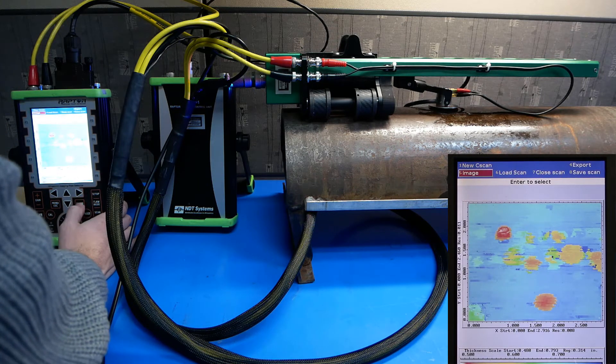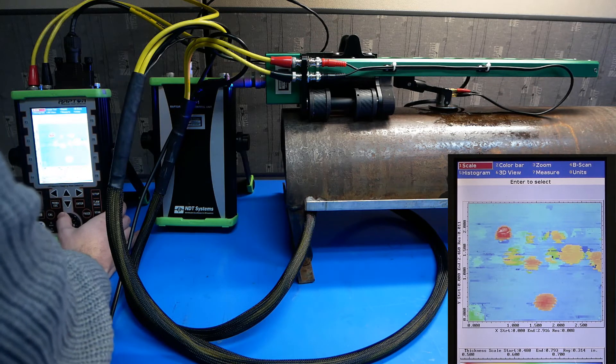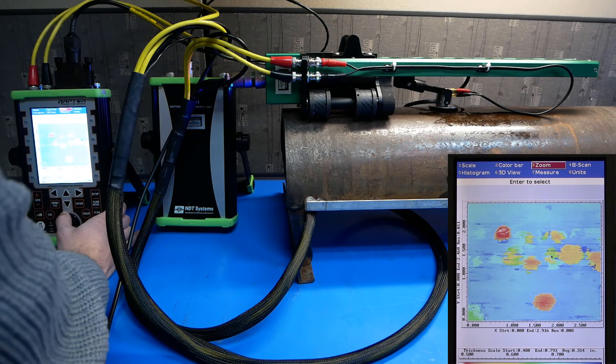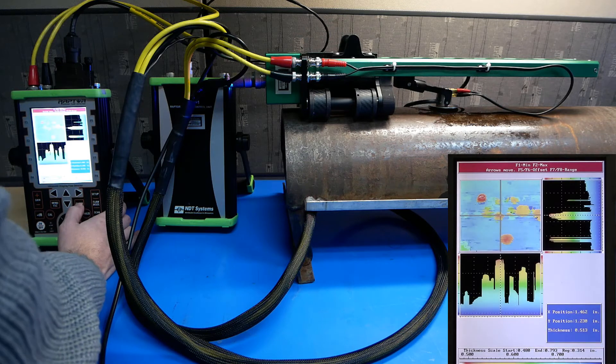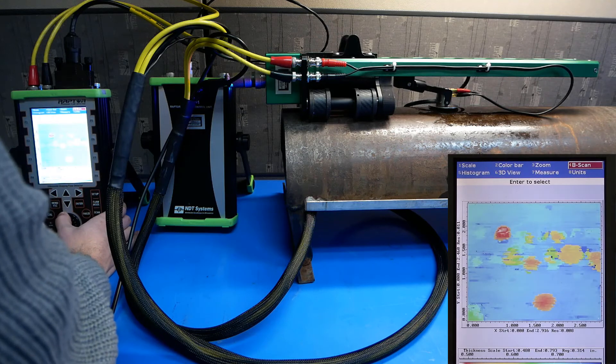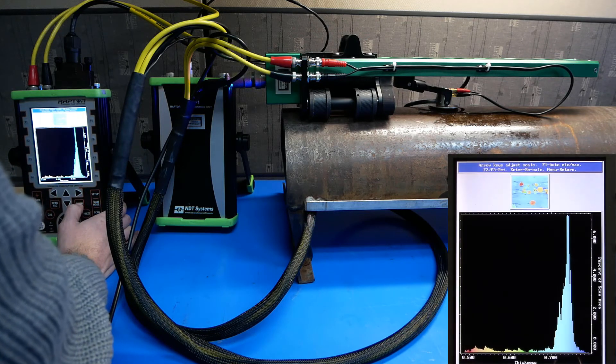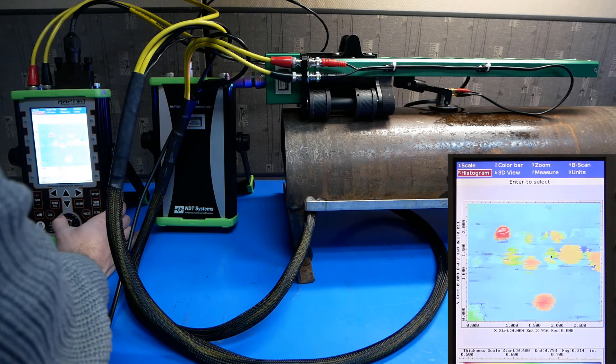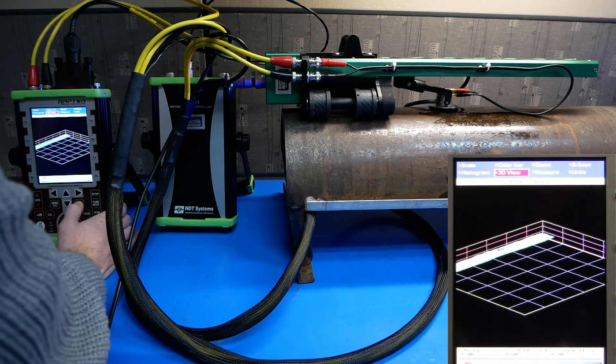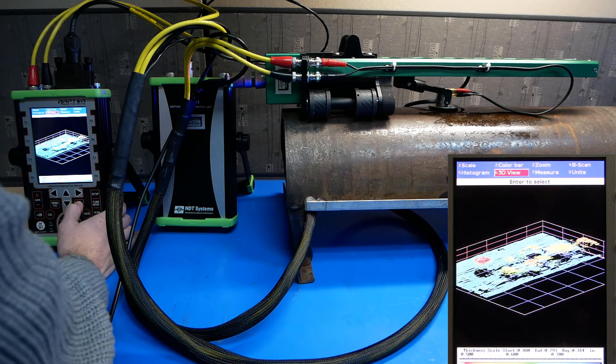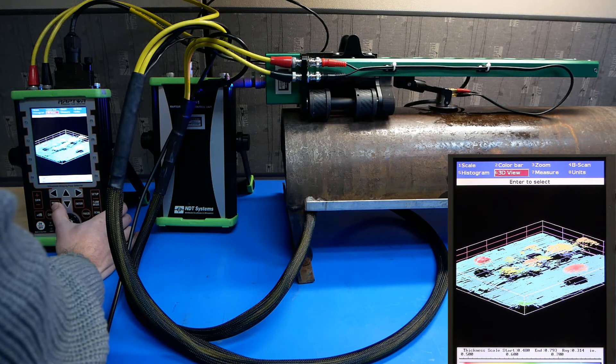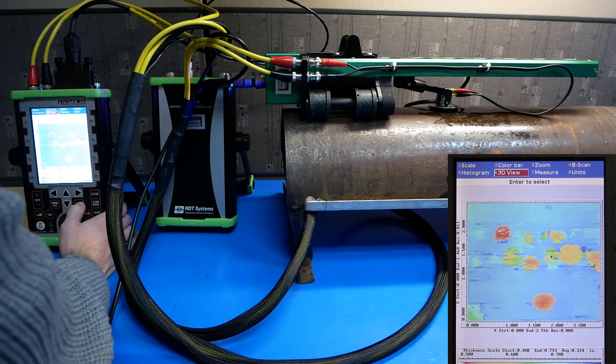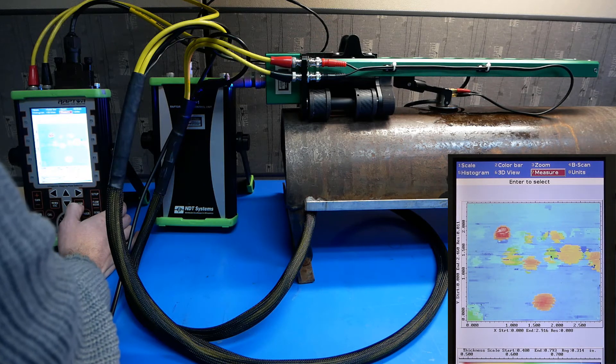We can also take a look at the image and manipulate it in a variety of ways by going to the image tab. We can change the scale, the color bar properties. We can zoom in. We can take a look at a B-scan generated from the C-scan data. We can take a look at a histogram of commonly measured values. We can populate the data in a 3D view. And we can measure any particular spot to find a thickness at a designated spot.